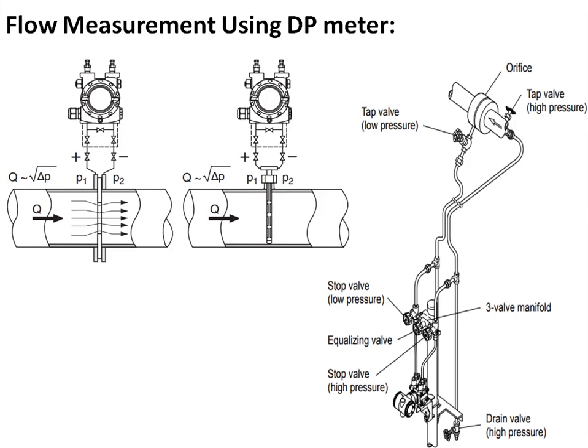The flow rate is proportional to the square root of delta P. The pressure drop in the pipeline caused by the primary sensing element is tapped to the DP transmitter through impulse lines on a three-way manifold.